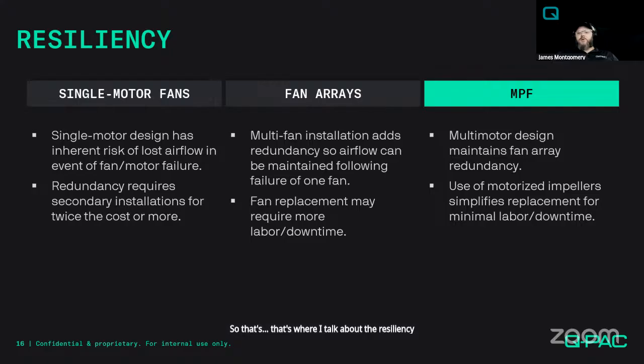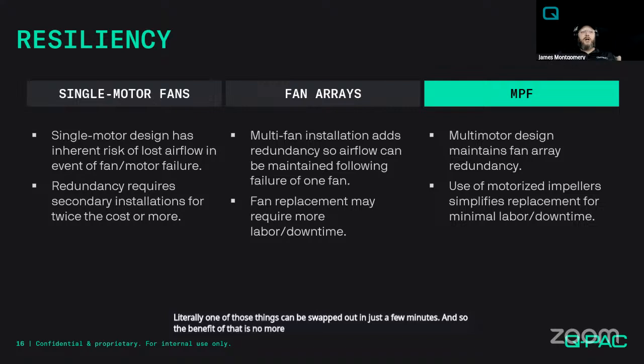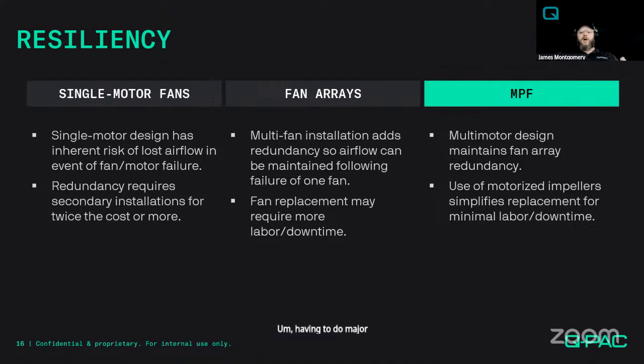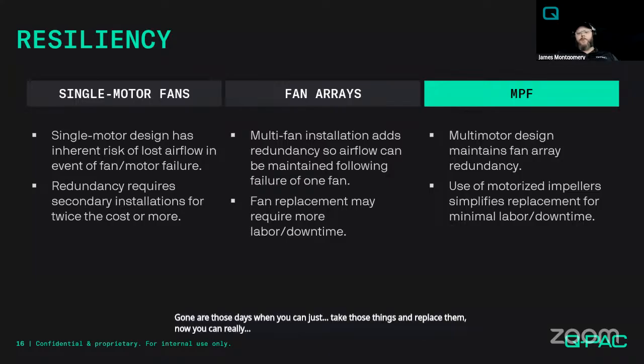And again, we use the motorized impellers, and this simplifies any kind of replacement time. So if you're at a site that does have an individual failure of one of these EC motors, literally one of those things can be swapped out in just a few minutes. And so the benefit of that is no more craning in large objects, rigging in large objects, having to do major shaft and bearing alignments and stuff like that. Gone are those days. Now you can really just swap in a small multi-motor system.